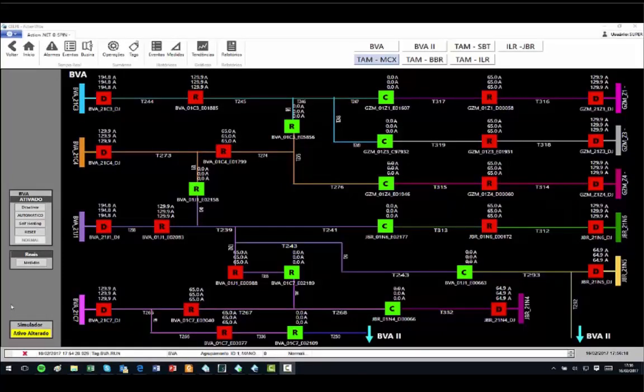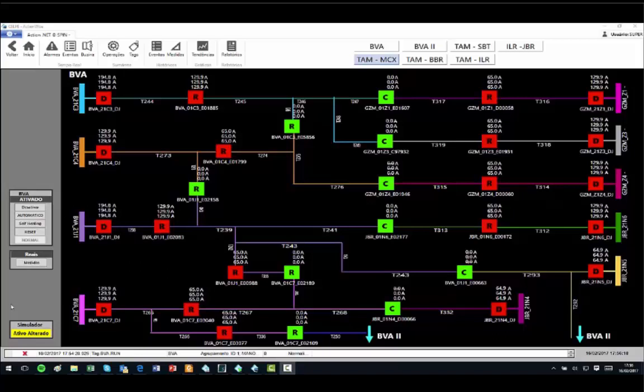In this way, we can simulate faults and switches and loads, and these information will be sent to ADMS FLISR, that will run the topological processor, the state estimator, and the contingencies FLISR module, and will suggest maneuvers to isolate the problem and restore the system.